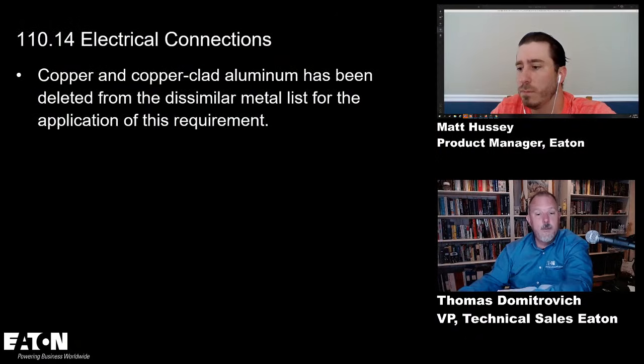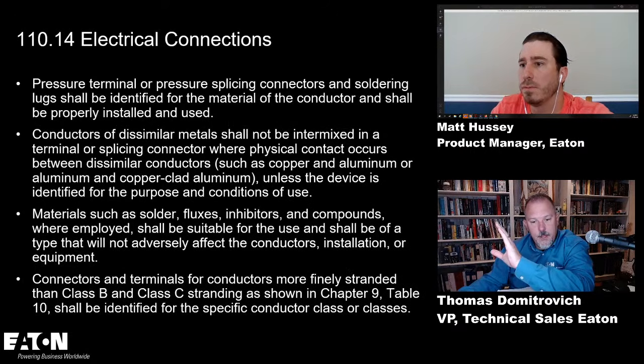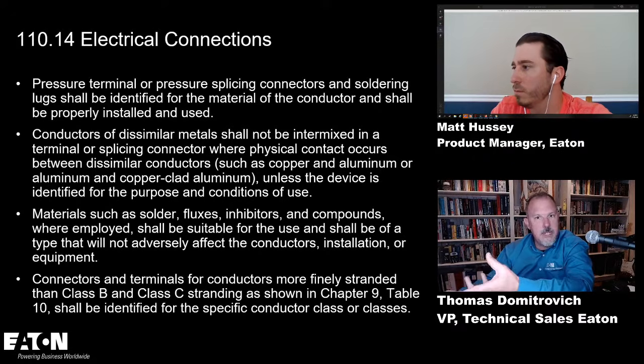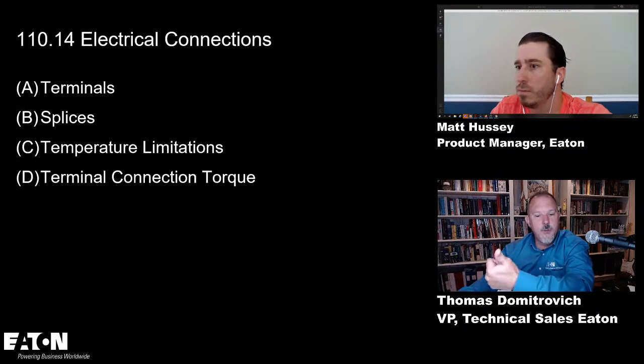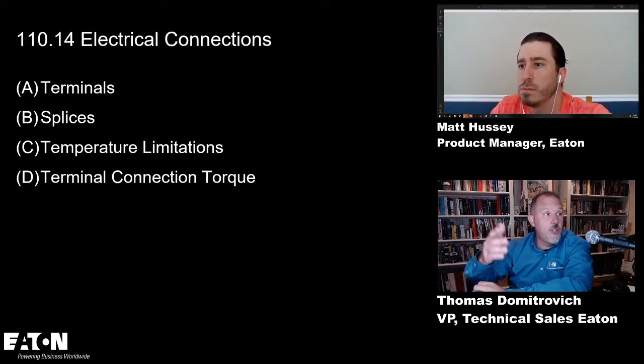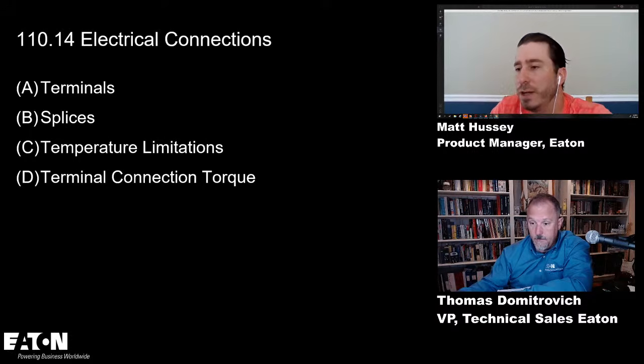110.14 talks about the terminations, and remember, 110.14 talks about torque and pressure connectors and how you pull things together. They have the terminals, the splices, the temperature limitations, which is really what we're getting to here in this discussion. Obviously you've got torque requirements. You published your torque requirements for the motor control center, right, Matt? Yeah, they're in that same manual we're looking at.